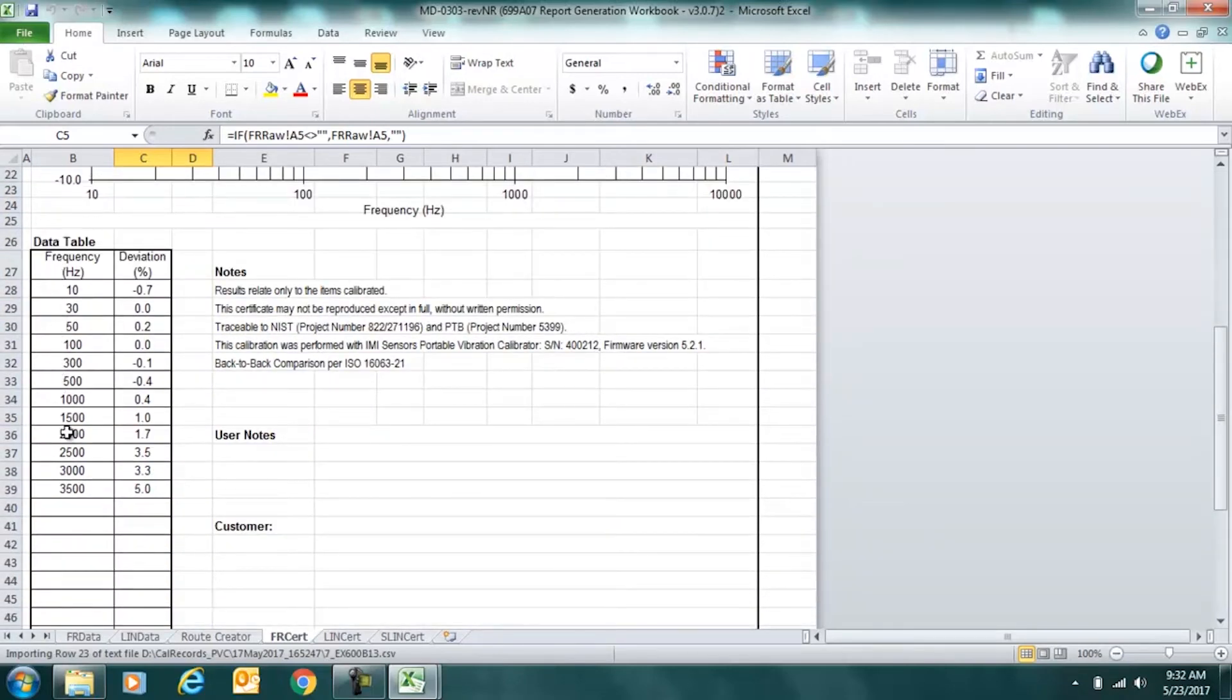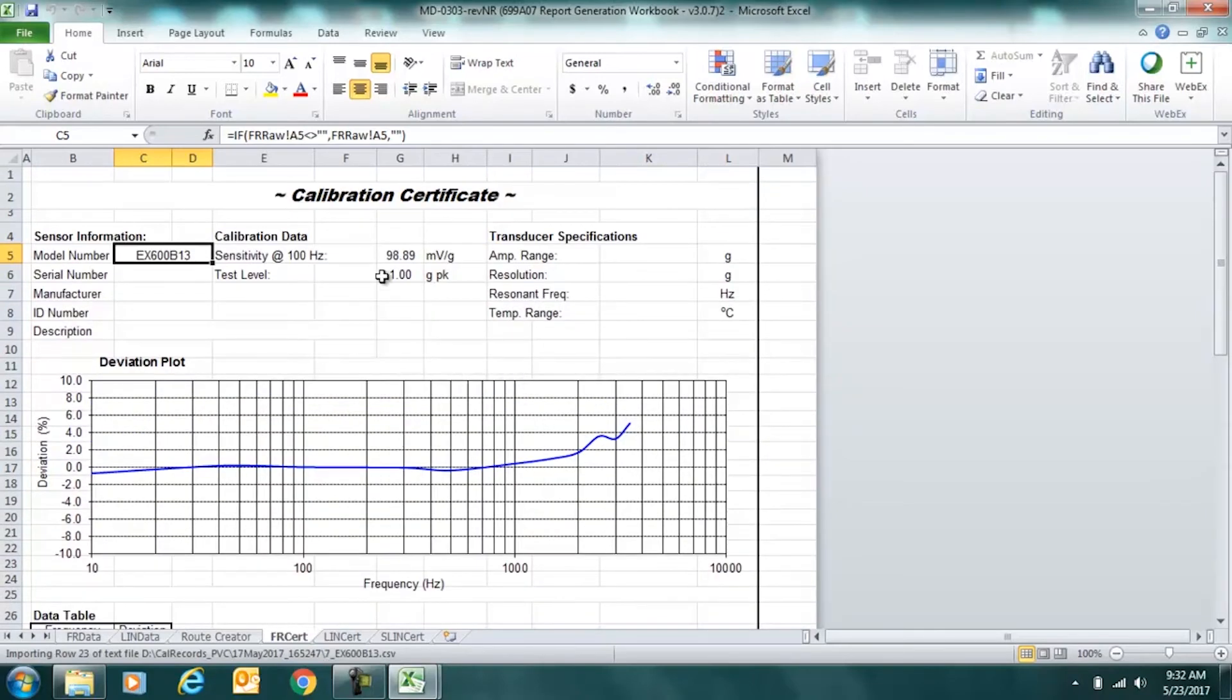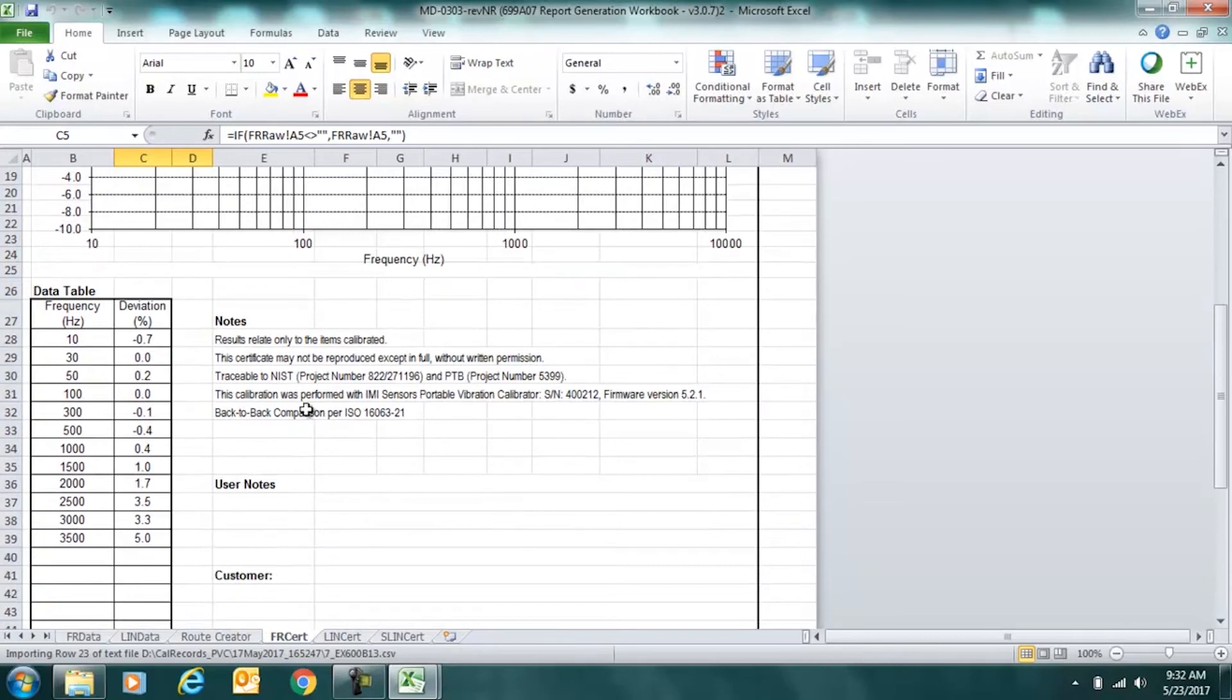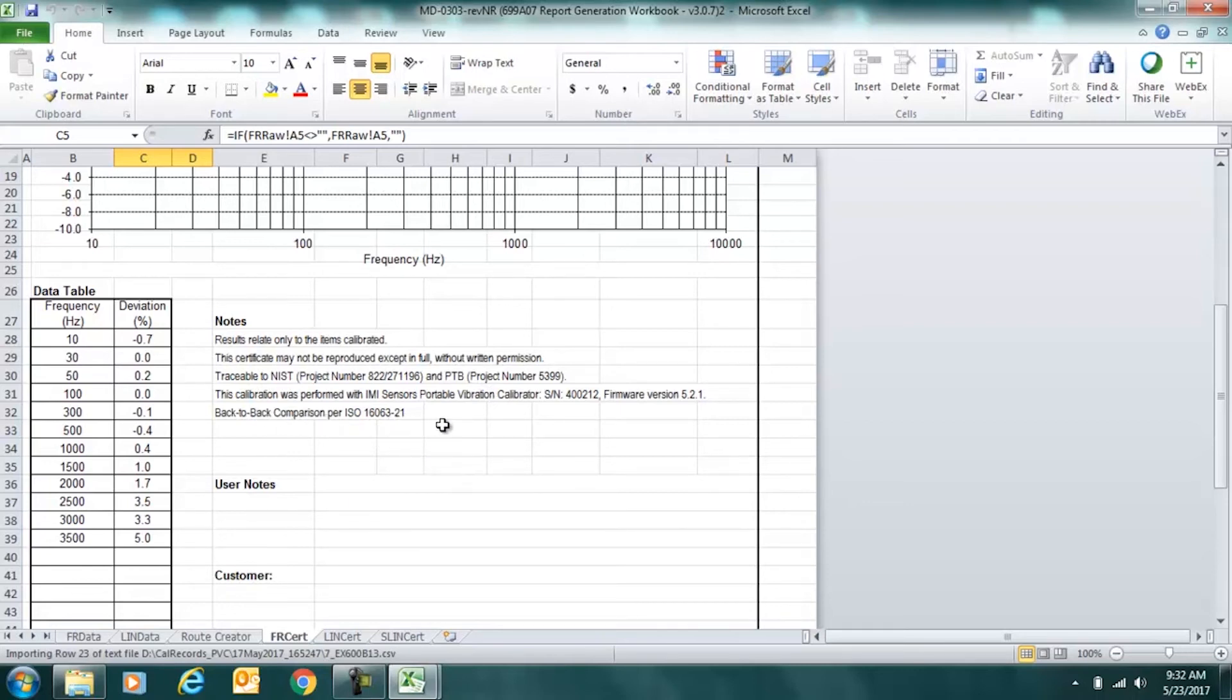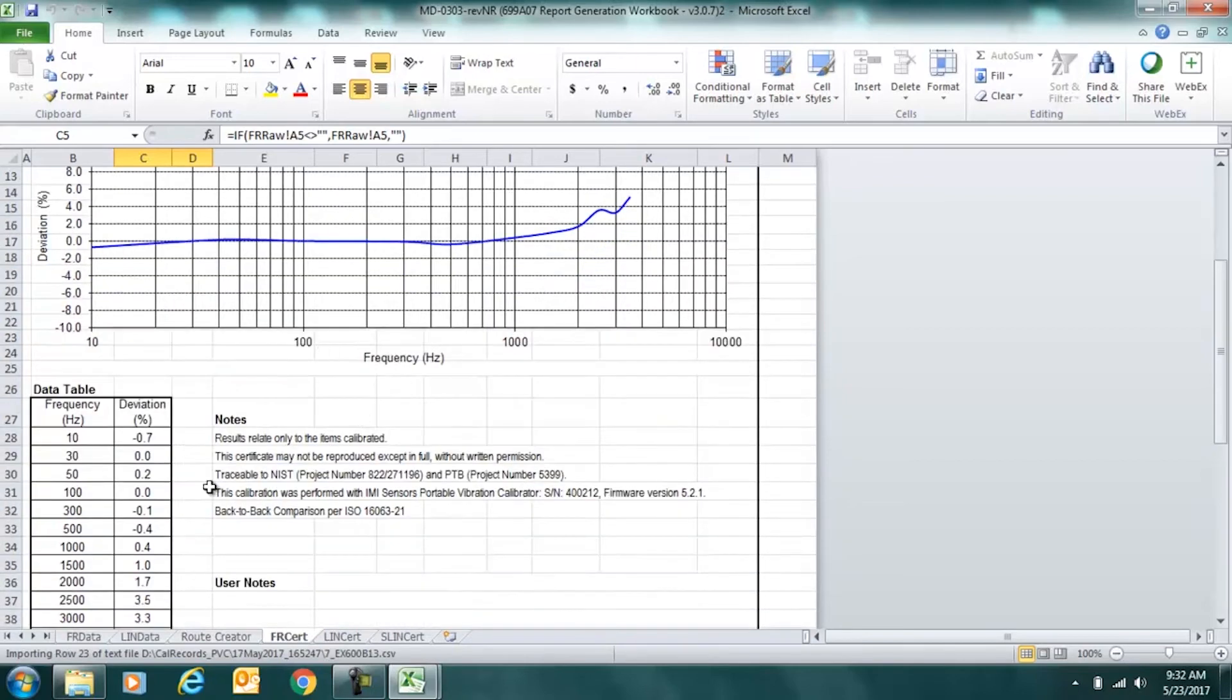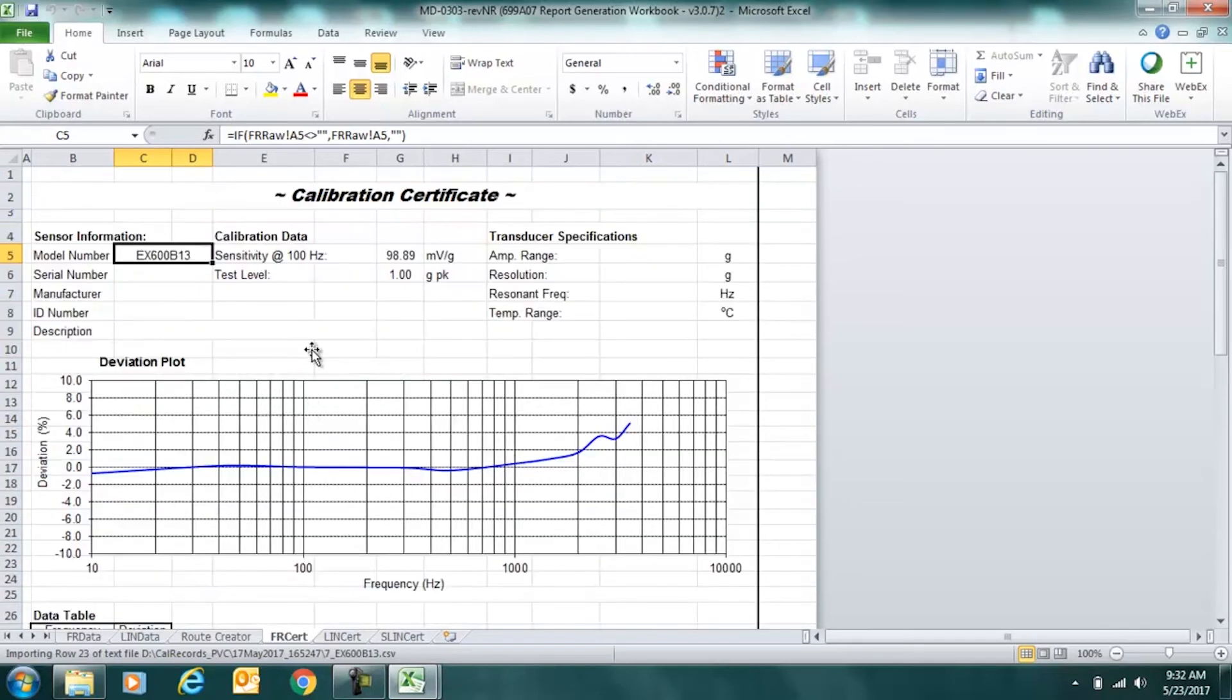The data table shows the percent deviation at each frequency from the calculated sensitivity at reference, which again is up here. Our notes give our NIST traceability and PTB project numbers. It also notes that this is a back-to-back comparison per the ISO standard 16063 part 21. The serial number and firmware version of the calibrator itself. The rest of the cells, other than data, so if I click on data, I cannot modify any of these cells and that's what makes this sheet ISO 17025 compliant.